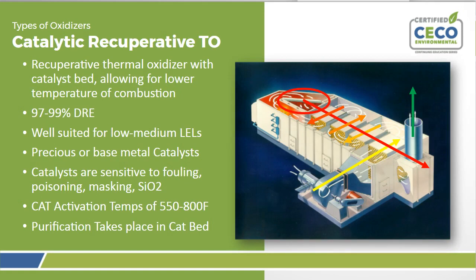Moving on to another variation, we have a catalytic oxidizer. This is kind of just to showcase the catalyst portion. This is a catalytic recuperative oxidizer, so again, it has that 4-pass heat exchanger. But here we have a precious metal catalyst bed, which resides in the combustion chamber. It's circled in red there. This allows for a bit lower oxidation temperature, around 550 to 800 degrees, as Brian said, rather than 1500 or 1600 degrees. But it does require custom tailoring for the process.